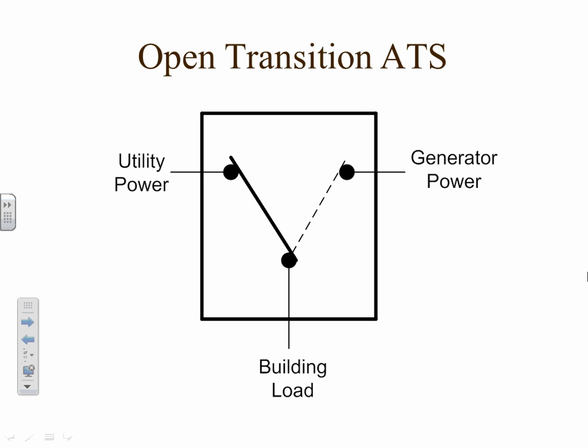And then finally, once we've transferred back, now we've gone from generator back over to utility, the generator's still running. Most modern engines today on generator sets are being squeezed for every ounce of horsepower they can get. So in part of doing that, you're going to see a lot of turbochargers on these engines, gas and diesel, both. These turbochargers run really hot, and they run directly proportional in temperature to the amount of load that's on them. So if we've been running in a building now off of this transfer switch, and that generator set has been operating near its capacity, it's pretty hot. And more importantly, the turbocharger on that thing is really hot.